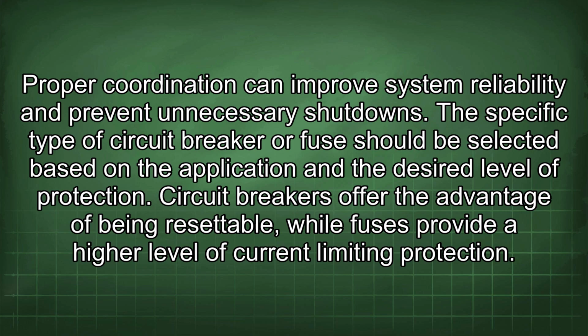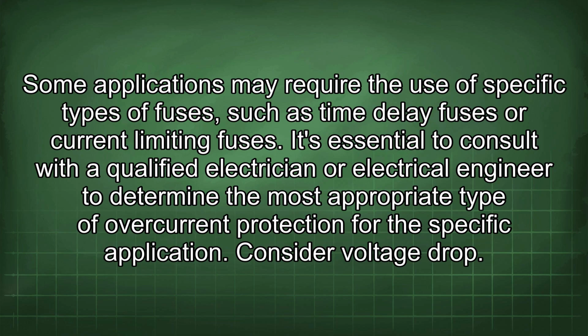A specific type of circuit breaker or fuse should be selected based on the application and the desired level of protection. Circuit breakers offer the advantage of being resettable, while fuses provide a higher level of current limiting protection. Some applications may require the use of specific types of fuses, such as time delay fuses or current limiting fuses. It's essential to consult with a qualified electrician or electrical engineer to determine the most appropriate type of overcurrent protection for the specific application.